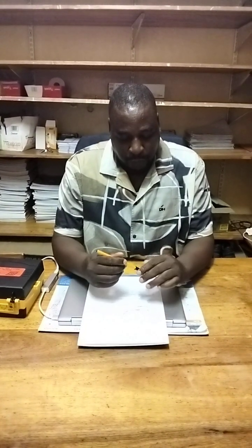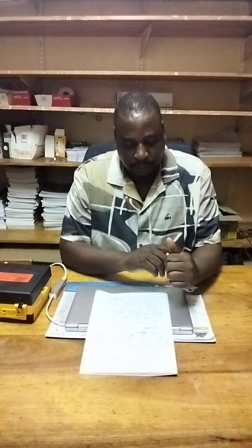The tests that the accredited person must be responsible for: test number 1 is continuity of bonding. Number 2, earth loop impedance test. Test number 3, operation of earth leakage unit and operation of earth leakage test button.